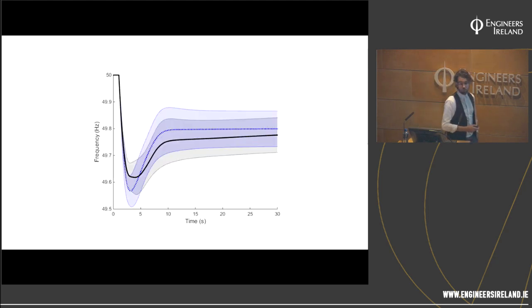Does this mean that a wind turbine, because of the inverter, can actually simulate a very high inertia compared to its size, because it can generate whatever frequency or speed it wants to? No, in that the source of energy is still finite. The only reason you can call it emulated inertia, in my view, is because the source of the energy is still the rotational energy of the machine. It's still what we call inertia. Now, it's synthetic, but a wind turbine, like anything else, has a limited amount of energy, and that's all that you can extract.